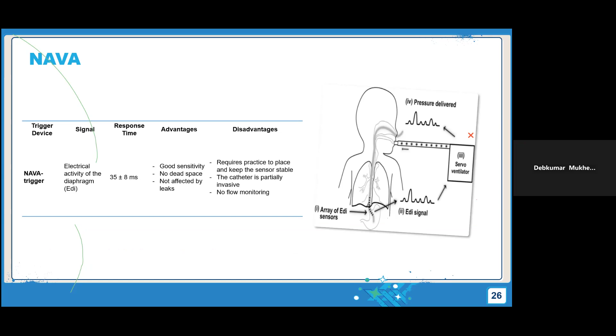So what about NAVA? These are the problems we have learned. One is that with flow triggering, there will be a lot of leak. In the case of pressure triggering, the patient will not be able to generate that much pressure change. In NAVA, the electrical activity of the diaphragm is detected by the machine, and the machine will deliver a breath. This is very highly sensitive. But one of the problems is that it is a little bit invasive, because a NAVA catheter is pushed, and one catheter costs around 12,000 or 15,000 rupees, and the catheter size also differs, and the machine delivers a breath. Next slide.